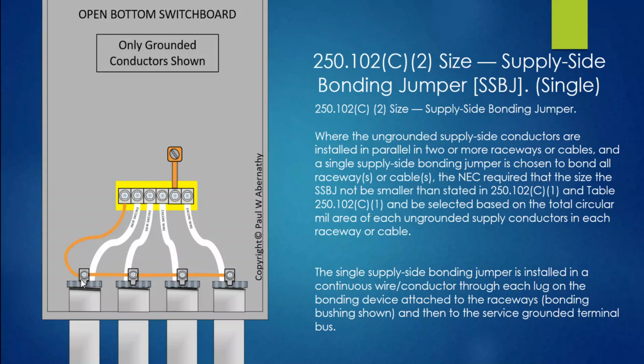All right, so I go 500, take the largest within this raceway. Incidentally, since they're parallel, they're all going to be the same size of the largest ungrounded supply conductors anyway. So 500 set, because of the parallel rules in 310, we're going to go 500 to 500 to 500, 500, or easy for you, you can take all of the 500s in phase A, because usually they probably separate it out. In this case, ABC, ABC, ABC, ABC. Anyway, long story short, 500, 500, 500, 500, that is 2,000 kcmils.